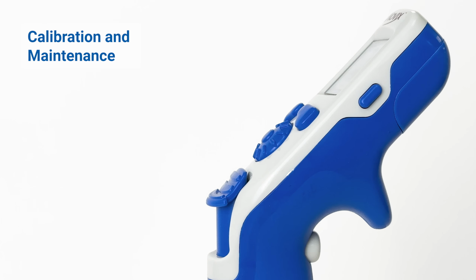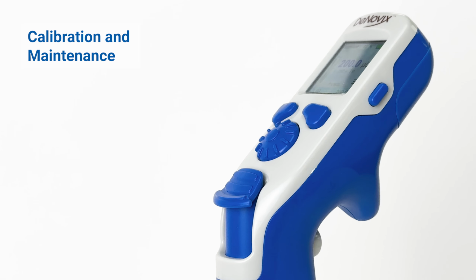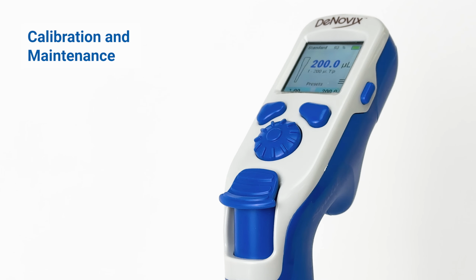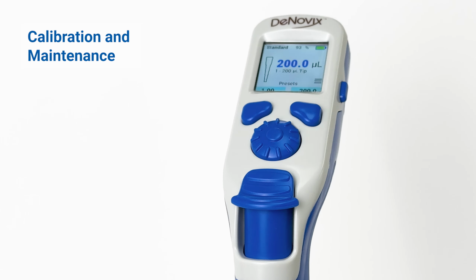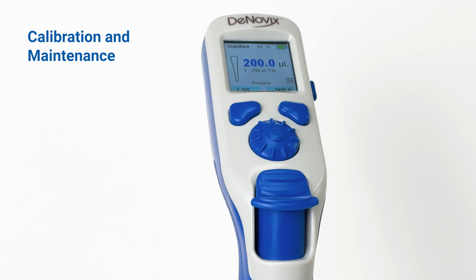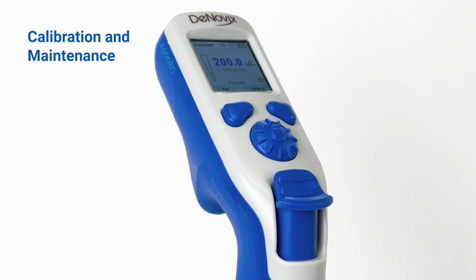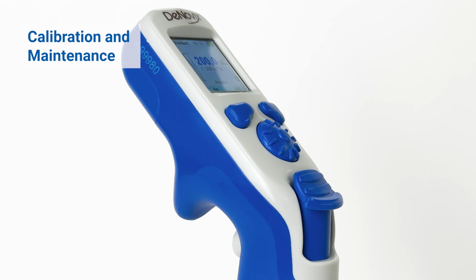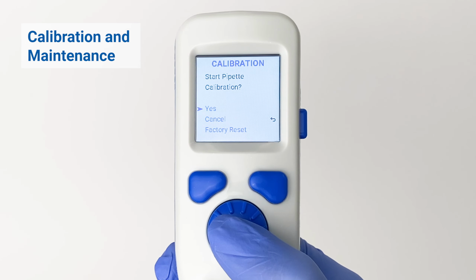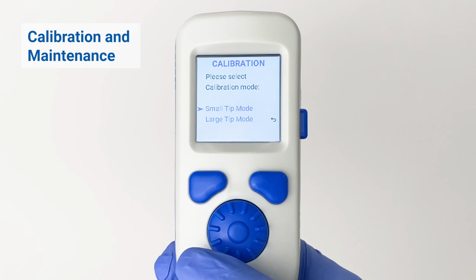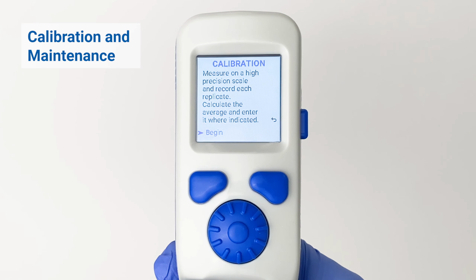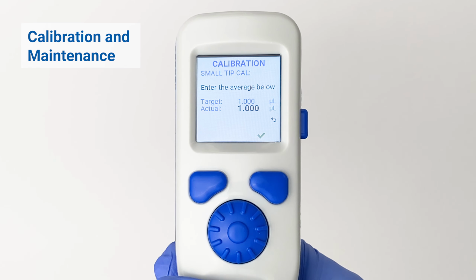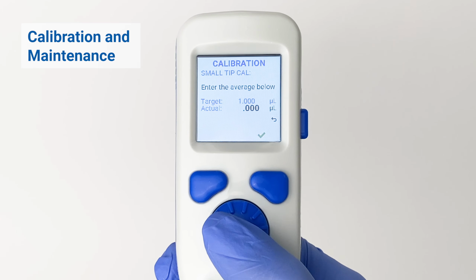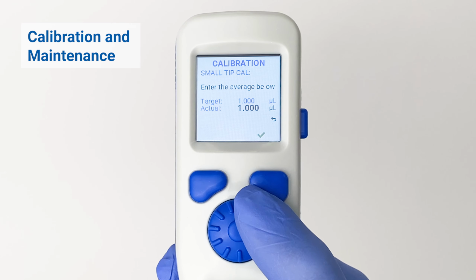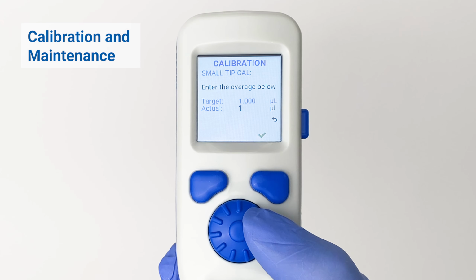The Squid Pipette is fully compatible with standard gravimetric calibration procedures performed by any accredited pipette calibration provider, integrating seamlessly into existing laboratory certification schedules. Follow the steps on the calibration screens to complete pipette calibration. Liquids should be measured on a high precision scale before the averages are entered into prompted locations.